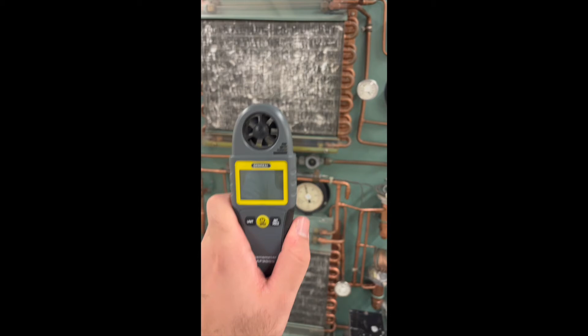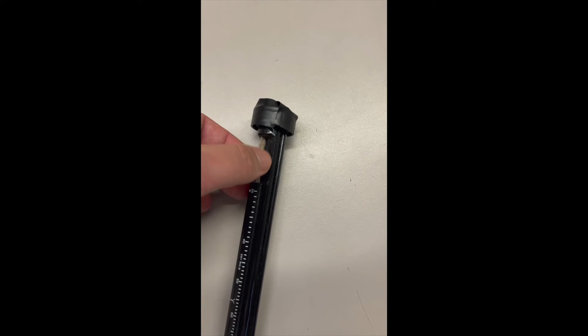The next device that I'm going to explain to you is again a temperature measuring device, but this time it is used to measure the wet bulb temperature of the air. How it works is that there is a storage tank for water that makes this material wet. Later on we are going to rotate it in front of our heat exchanger to find the wet bulb temperature of the outcoming air. As you may know, the wet bulb temperature is related to the humidity of the air. More humidity, less difference between the wet bulb temperature and the measuring temperature. And with less humidity, this difference will be larger.